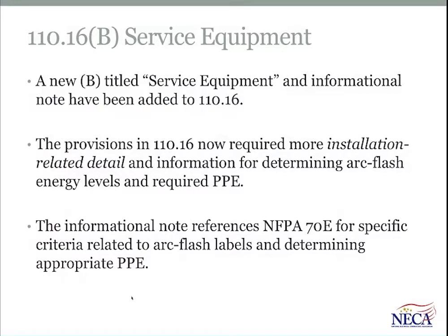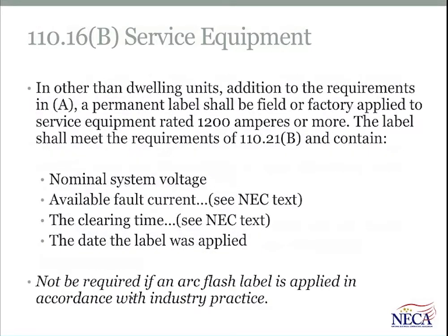Moving right along in 110, Section 16, not a new section to the NEC. This is the section that deals with arc flash hazard warning markings. A new subdivision B titled Service Equipment has been added and an associated informational note. And what this new subdivision requires is, for larger equipment, some additional installation-related criteria or detail for determining arc flash energy levels and required PPE when the table method in NFPA 70E is utilized. So what you're going to see in this subdivision is a 1200 ampere threshold. So that's an indication right away that you're dealing with services where you've got a higher energy level.